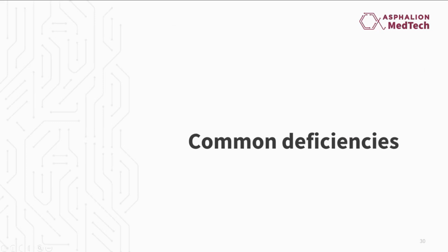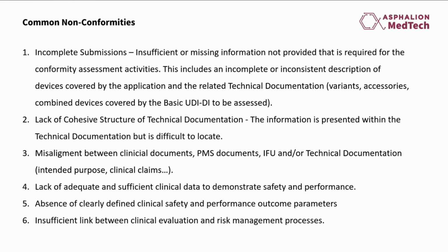And finally, just to close this part on European medtech requirements, I wanted to close the session, this part, with the most common deficiencies that we see for medical devices in the industry. First of all, we see that when they submit technical documentation to the notified body, the documentation is incomplete, because maybe some documentation is missing, or maybe it's not clearly identified. For this, our recommendation is to empathize with the notified body reviewer, because the easier you make their task of reviewing, the more chances of success you have.